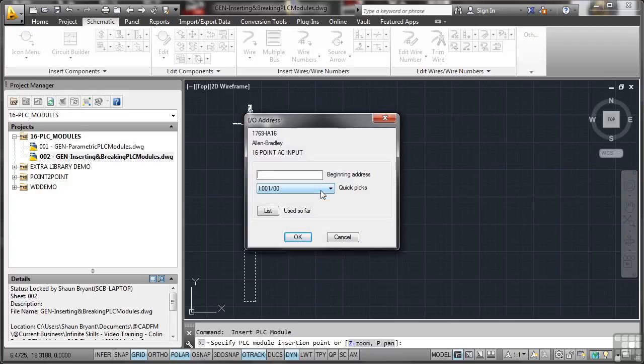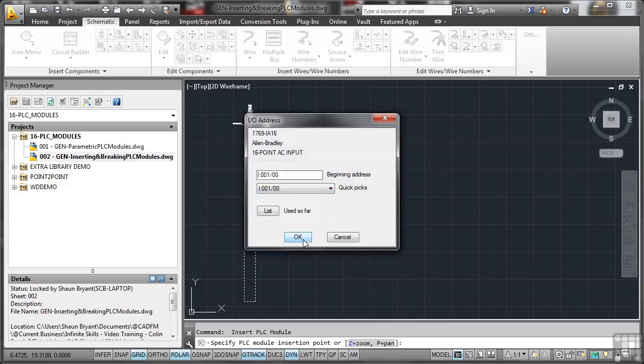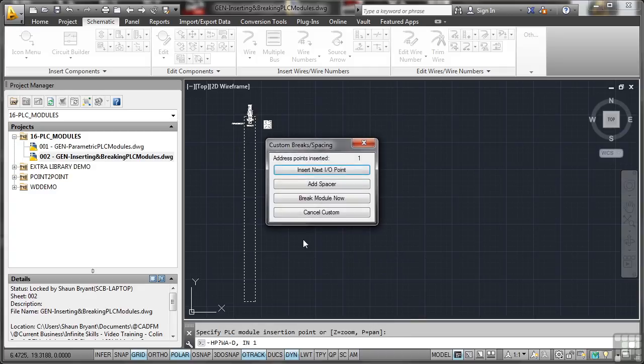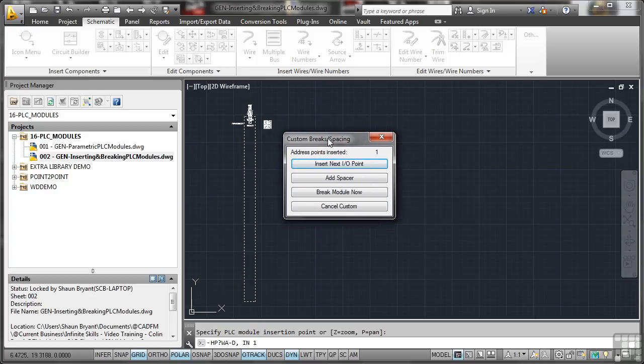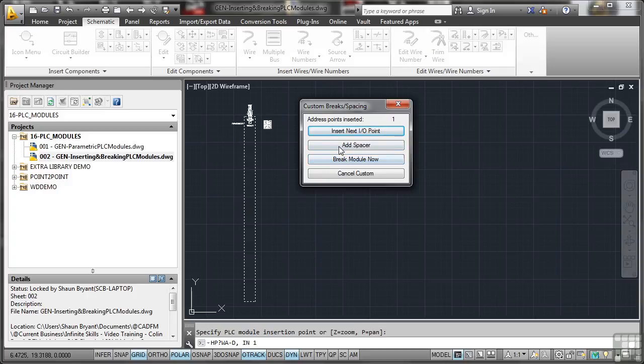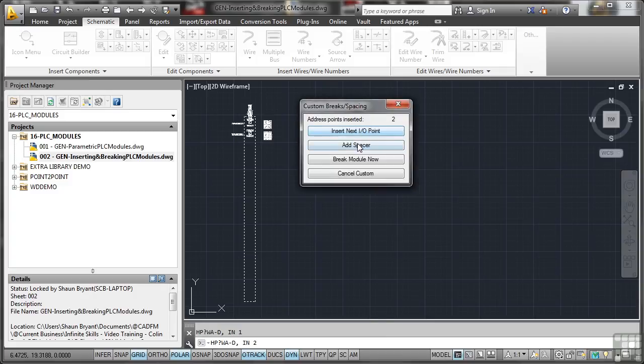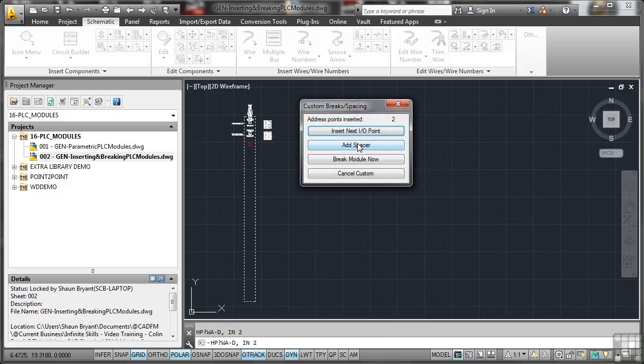And then it asks me for the beginning address. I'm just going to pick the one at the top of the list. Because again, this is general. I'm not worried about specifics right now. Now this is where it's cool. Because it's parametric, I can basically work my way through this and decide where to insert the next input output point, where to add spacers, and where to break the module. So I'm going to go insert next input output point, which is number one. Address points inserted there. So I click there and it adds the first one. I add a spacer. There's the red cross for the spacer.